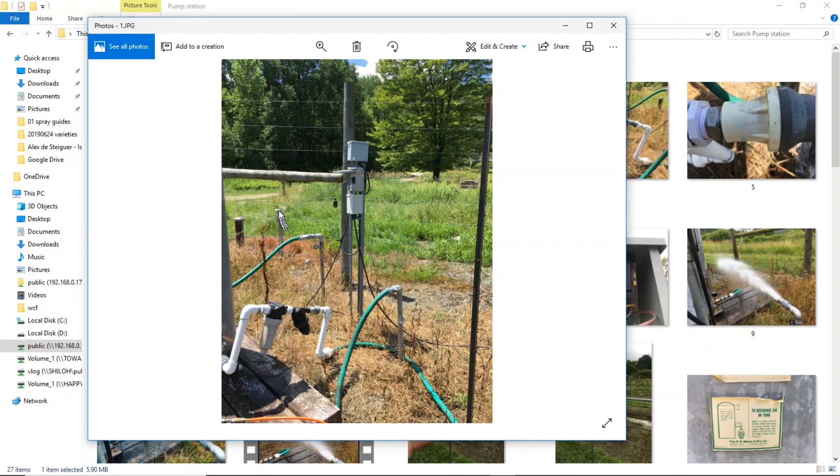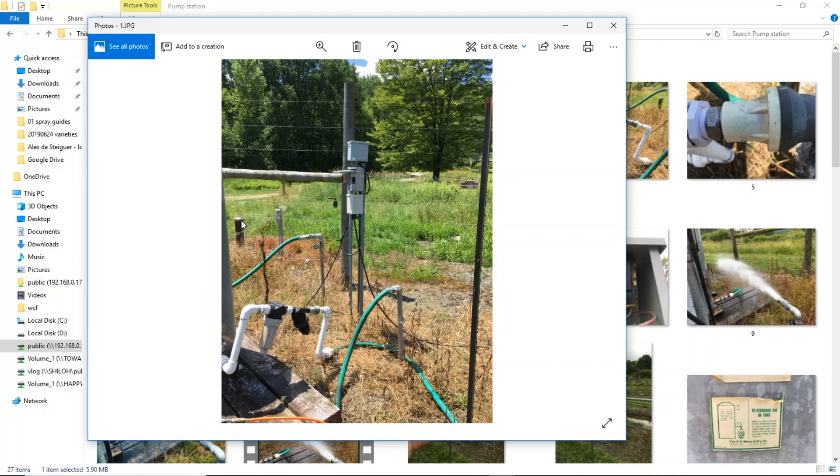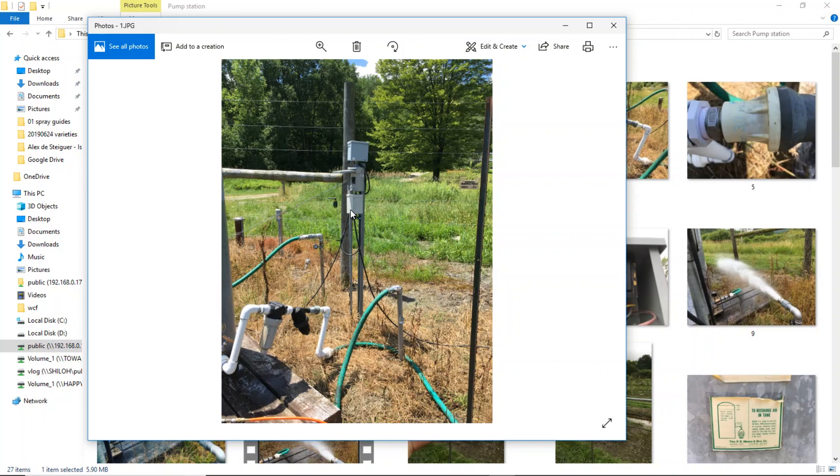Everything is in rigid conduit buried—schedule 40 real pipe, galvanized steel. There's one descender that goes to the well cap. Another descender comes up and rises up to this electrical control section which has three portions. One is a 30 amp twist lock connector, a standard generator 120 volt 240 volt twist lock that provides both the neutral and the ground. The ground is really important for safety.